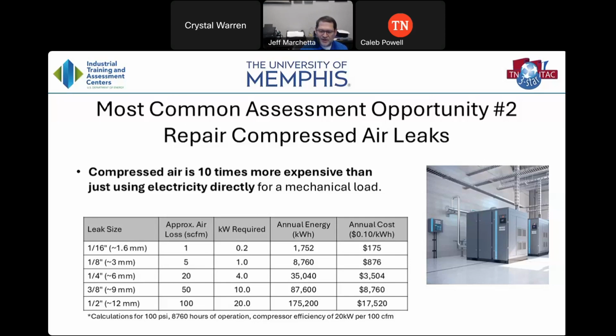Given the assumptions that we're operating at 100 psi pressure, which most compressors that I see in small and medium manufacturers are operating between 100 and 125 psi, typically rotary screw. Compressor efficiency 20 kilowatts per 100 CFM. That's fairly standard for a modern compressor. But long story short, if you're factoring in an electricity rate of, say, 10 cents per kilowatt hour, you can see that a 1/2 inch hole, under those assumptions, is an $18,000 leak, right?